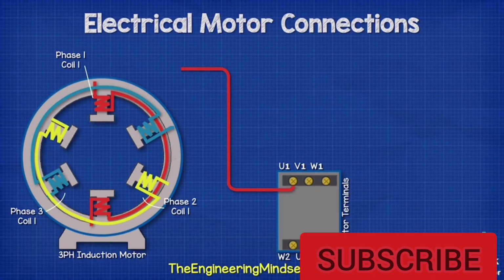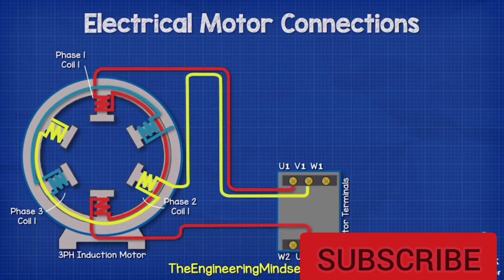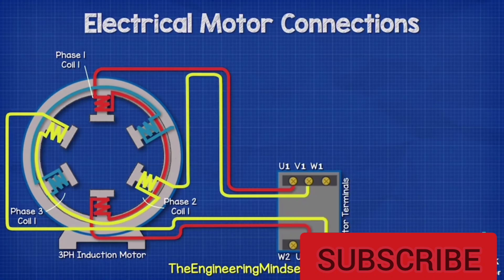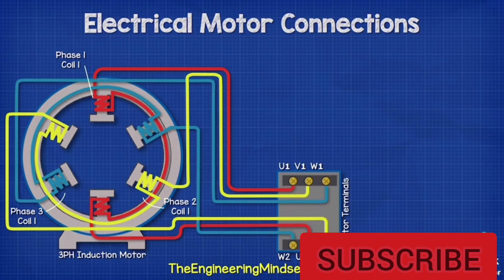We have our phase 1 coil connected to the 2 U terminals, then the phase 2 coils which are connected to the 2 V terminals, and lastly the phase 3 coil which is connected to the 2 W terminals. Notice that the electrical terminals are arranged in a different configuration on one side to the other. We will see why that is in just a moment.